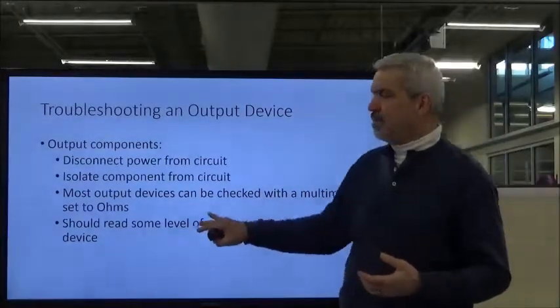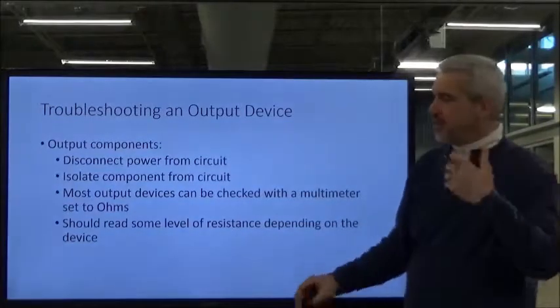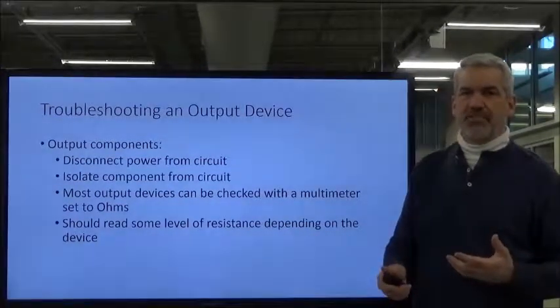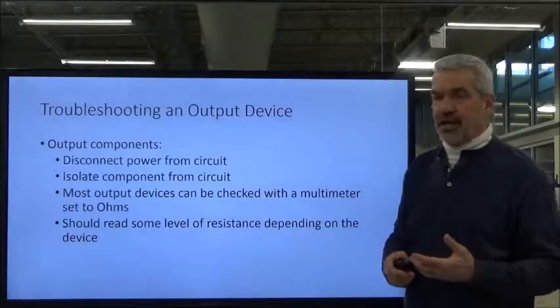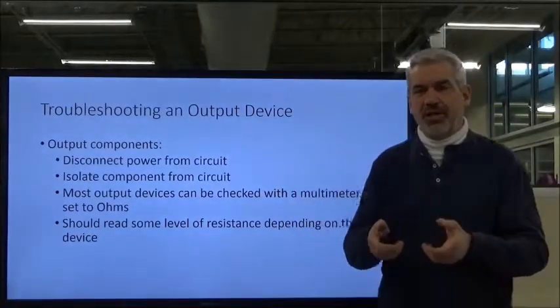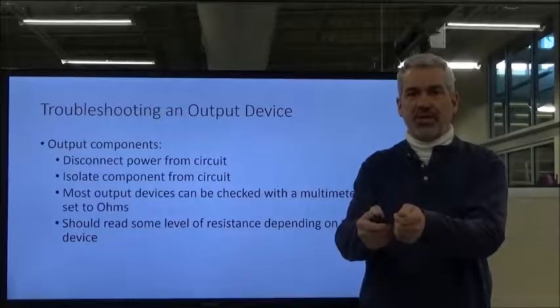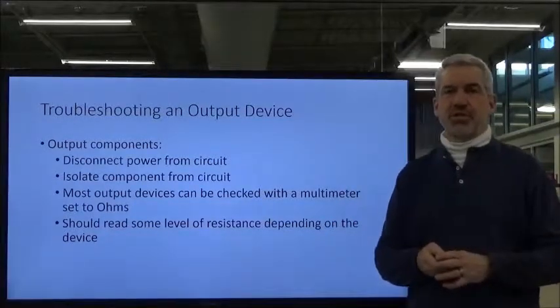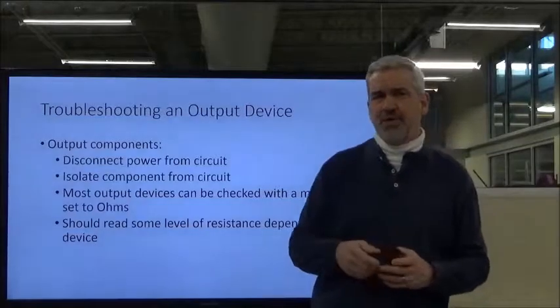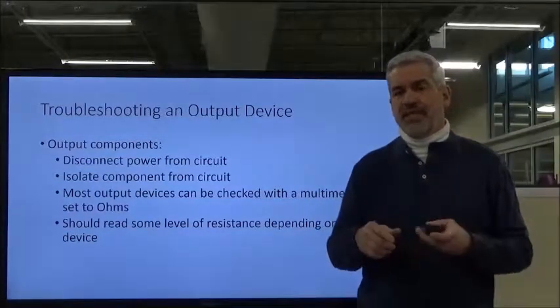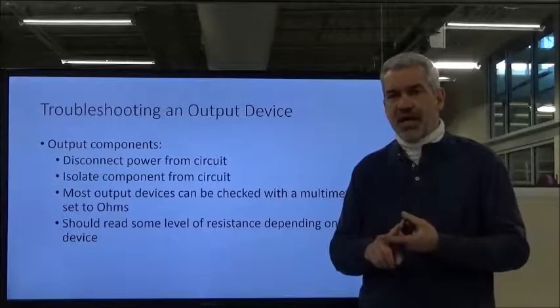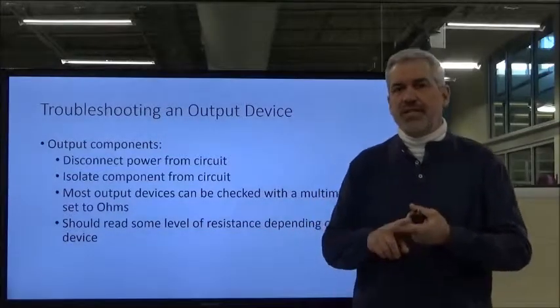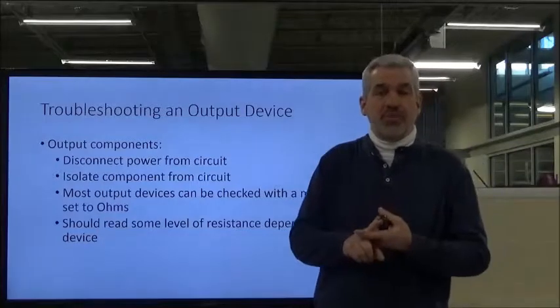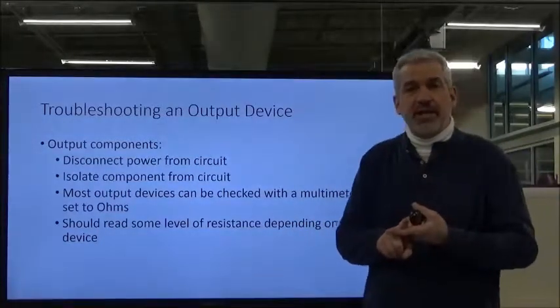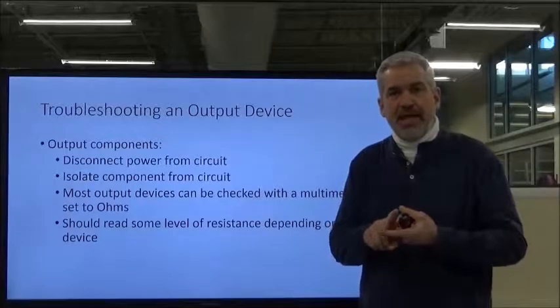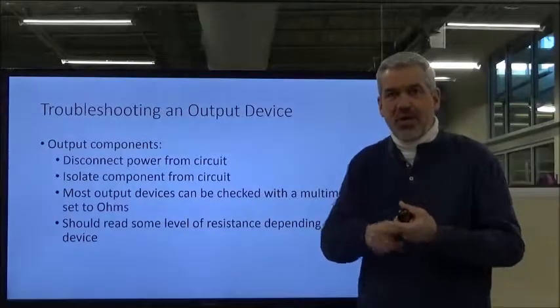When you take it out and isolate the power, you want to check that it's got the proper amount of resistance. If you put your ohm meter on there and read nothing between your two coil leads, you've got an open in your circuit. Sometimes with a shorted circuit, the coils have come in contact—the insulation has rubbed together—and instead of going the full length of the coil, electricity finds the path of least resistance, like water, and bails out of the coil to neutral wherever it's shorted.